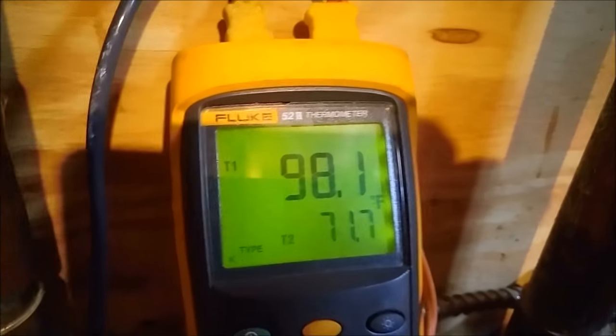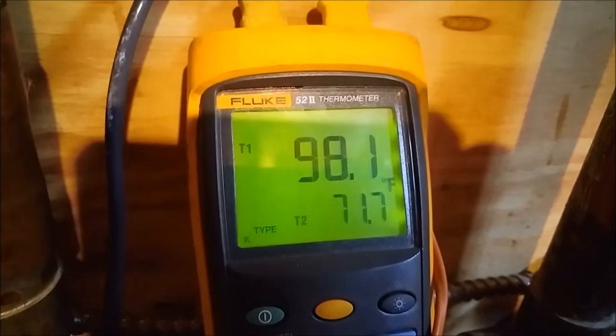Okay, we're up and running. This boiler just can't produce enough heat — it was engineered way wrong. I've got all this floor heat, all of it. Right now I'm just running the basement slab. That's my supply temperature — the boiler just started up, let me give it about 15 minutes and see what it does. It doesn't heat up fast enough. That's a mixed temperature — there's a mixing valve in there.